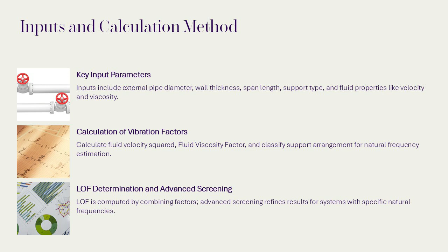Mechanical excitation occurs when piping is connected to or near machinery, such as pumps, compressors, or engines. LOF values are assigned based on equipment type: reciprocating compressors or pumps, 0.9, diesel or gas engines, 0.8, screw machines, 0.6, centrifugal pumps, 0.4, and electric motors, 0.2 to 0.4 depending on size. If detailed dynamic analysis confirms no frequency coincidence, LOF can be reduced to 0.4.